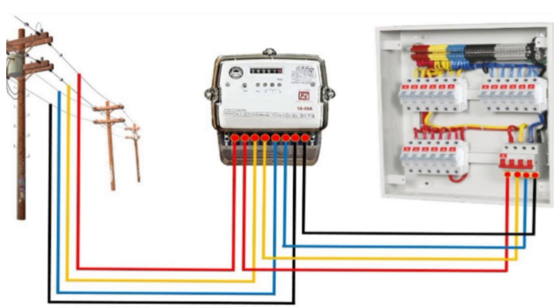There are two ways to apply diversity factor. After calculating the sum of all individual loads, you apply the appropriate diversity factor. Alternatively, you can group the loads differently and apply appropriate diversity factors to each load group, then add them up to get the total load demand. The diversity factor you apply to one wiring circuit may differ from that applied in another wiring.